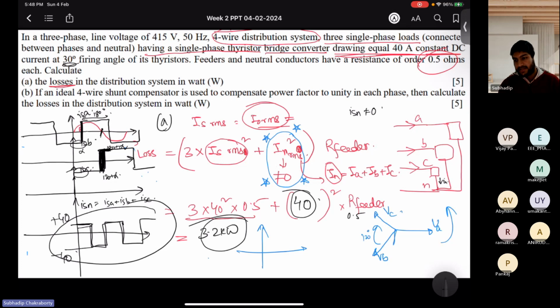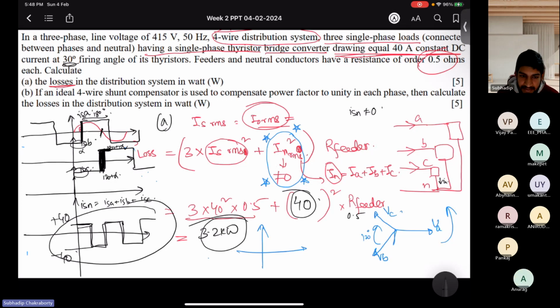These harmonically distorted currents and neutral currents, circulating currents, all are leading to line losses. So we want to minimize these line losses. That's why we are learning power quality. So this much loss is coming, 3.2 kilowatts without any compensation, if you see.